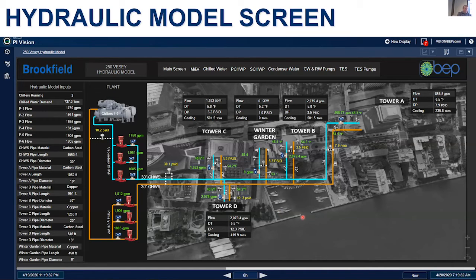So I could, if I wanted to, throw a differential pressure transmitter right here, and it's going to grab that data from pipe flow and put that calculated value. And the model's calibrated, so it's a pretty accurate value at this point.